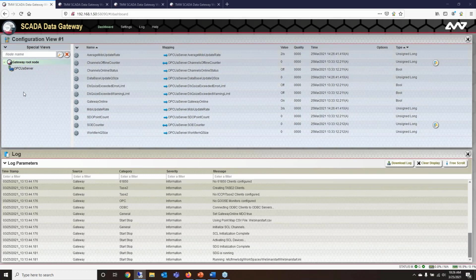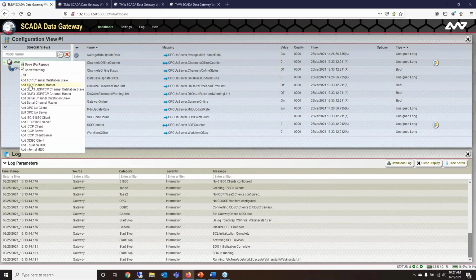So let's go ahead and get started. The first thing we want to do is get my Modbus server's data into the SCADA Data Gateway. To do that, we're going to need to create a master Modbus. So you just right click here, and then we'll do an Add TCP Channel Master.